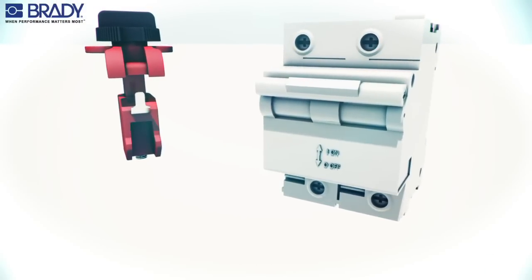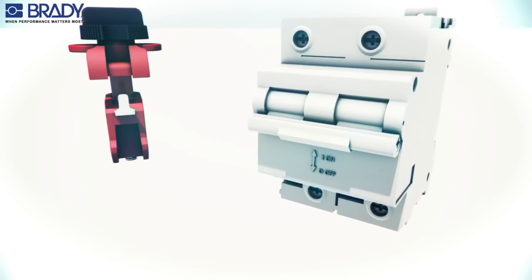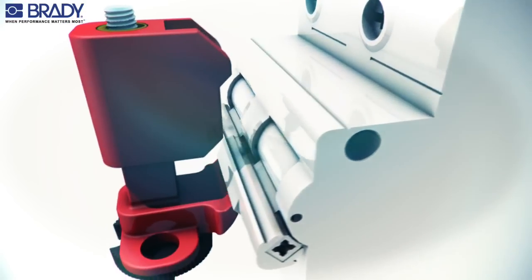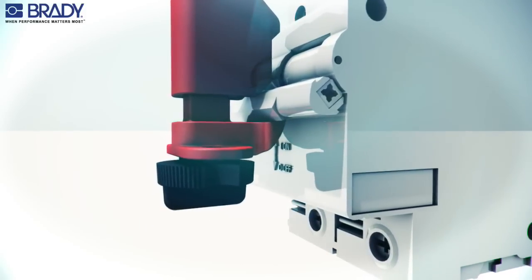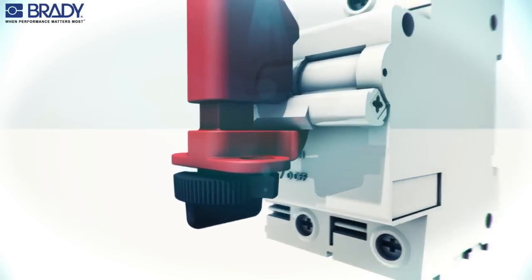Tie bar method: Place the circuit breaker in the off position. Put the metal clip under the tie bar and between the poles. Rotate the thumb wheel clockwise to secure the lockout device to the circuit breaker.